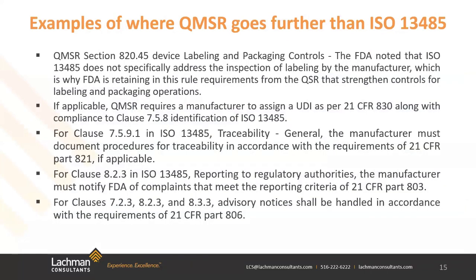Okay, so Deanna has talked a little bit about where the FDA is going to retain some of the other acts and parts of 21 CFR. So we're just going to go down through these fairly briefly. The first one we have is labeling and packaging. The FDA have opted to retain 820.45 because they didn't believe ISO 13485 went far enough, specifically to address the inspection of labeling. So that's been opted to hold on to.